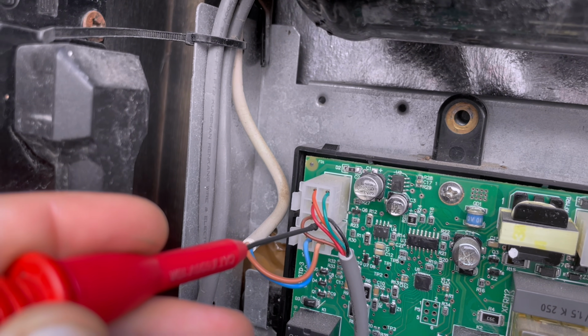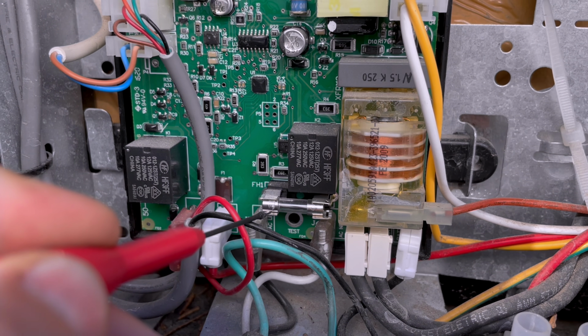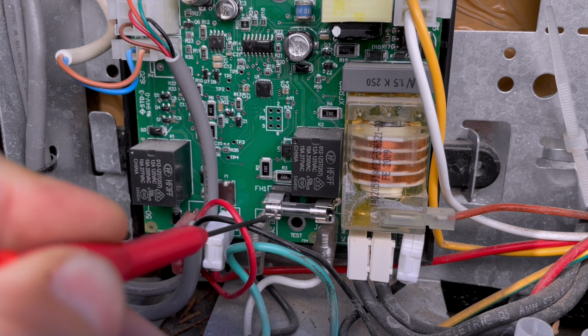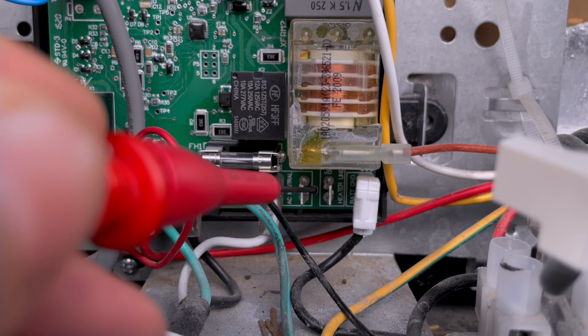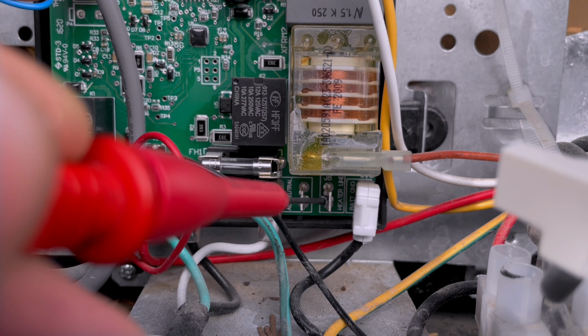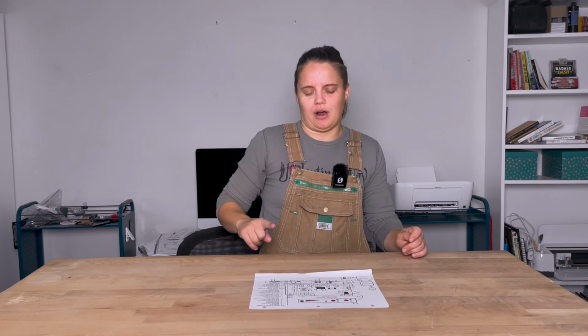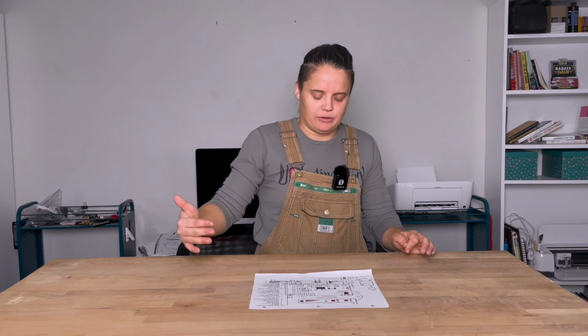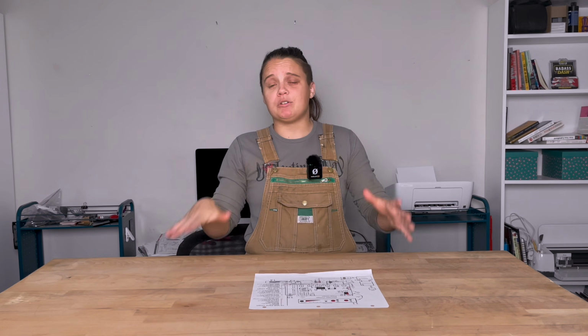So if you have 12 volts on this black pin and 120 volts AC on this fuse, but you're not getting 120 volts on this heating element pin, then it's most likely that the relay is your problem. Unfortunately, we can't just switch out the relay, so you most likely are going to have to switch out the whole circuit board. The one thing you can do is just try to give that relay a little flick.